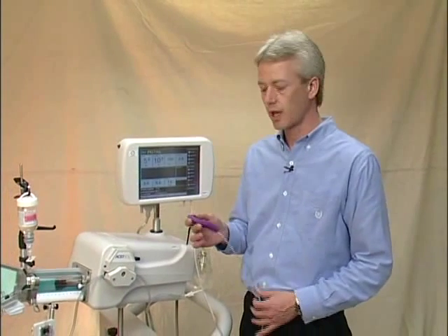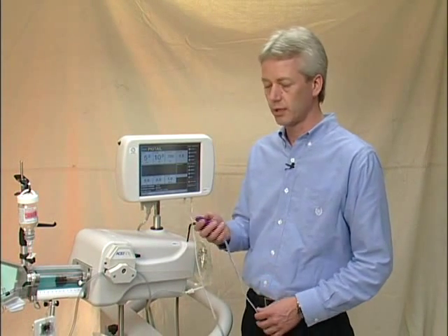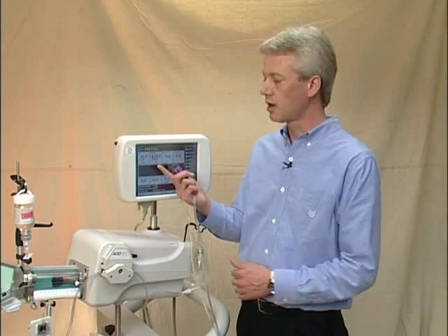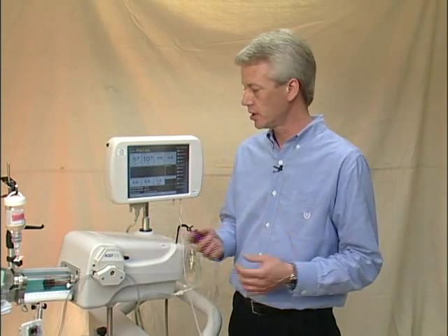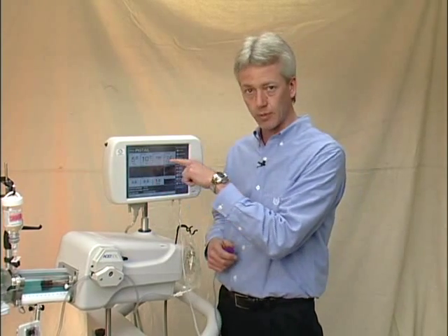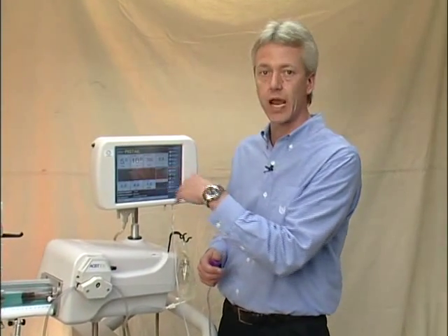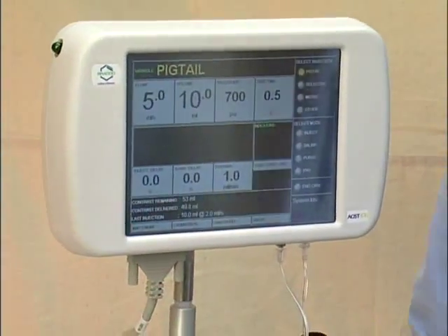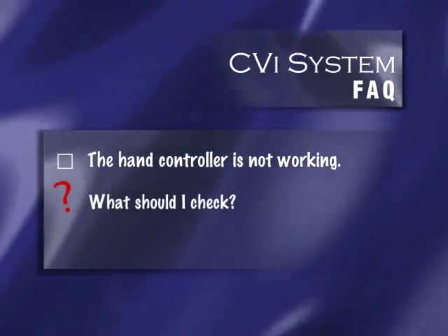And generally, the cause of that is their operation of the hand controller. Usually they are convinced that they have to use a larger than what we expect to be normal amount to still get a good image. Remember that these are the maximum limits on here, so this is as much as you're able to deliver. Another important way to save contrast with the system is to be liberal with your purges, especially the initial setup purges of the system.